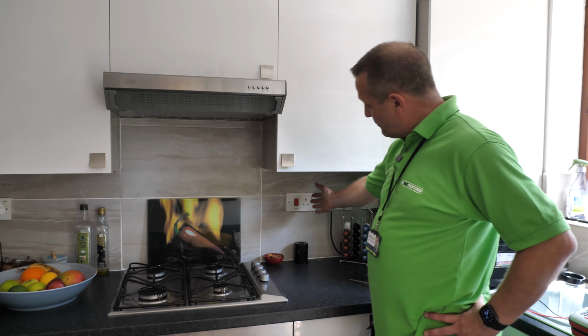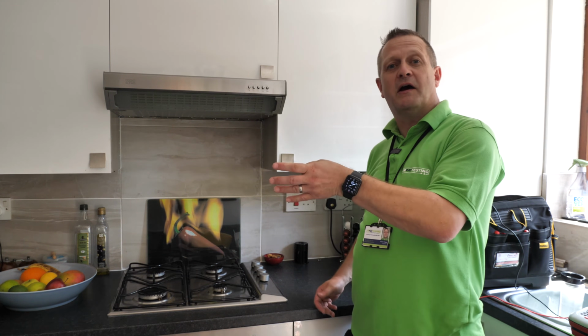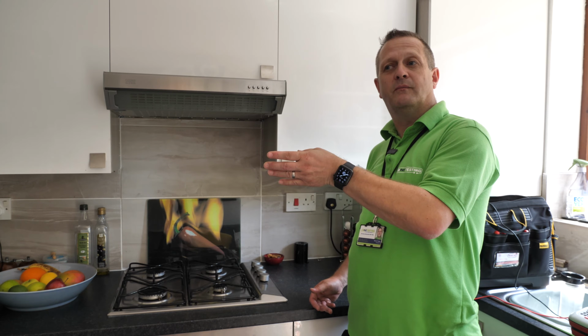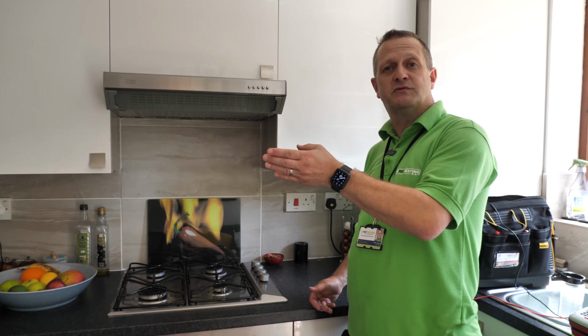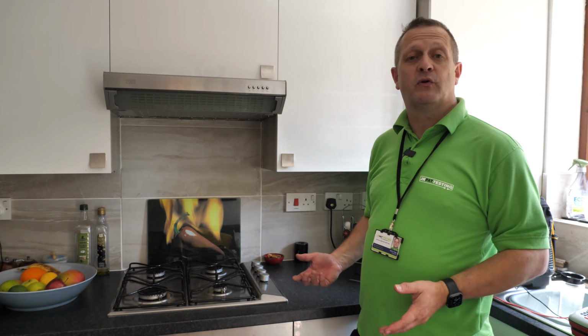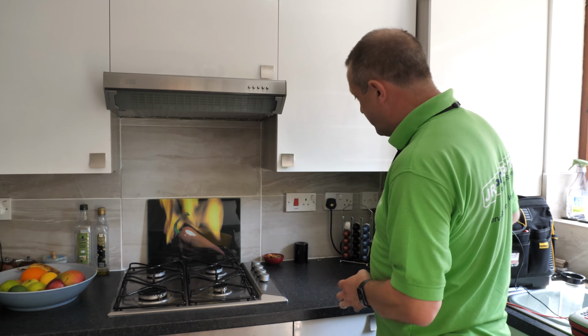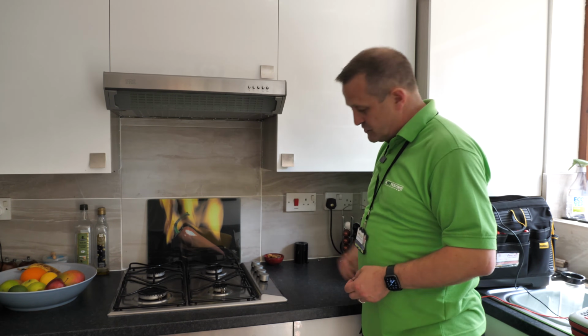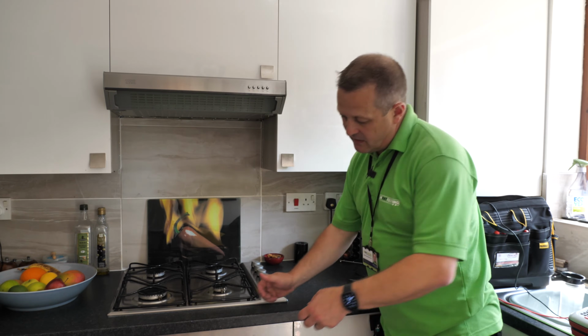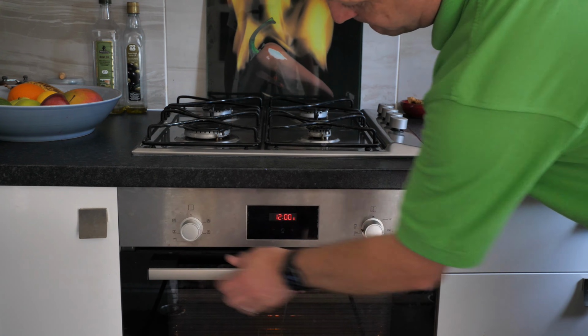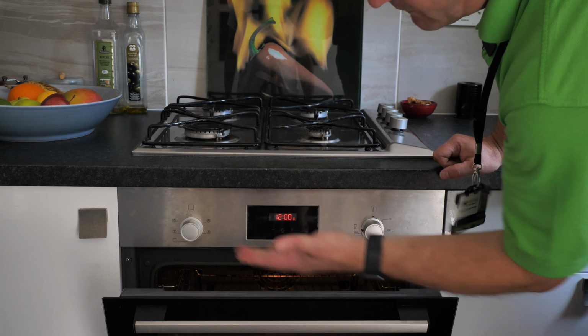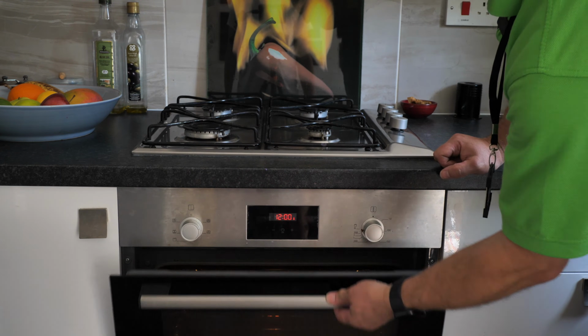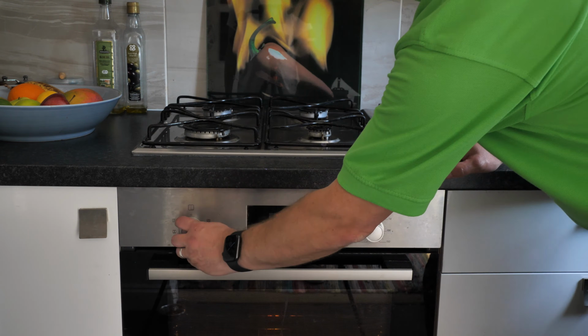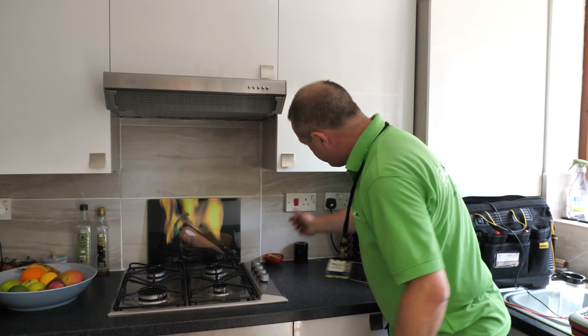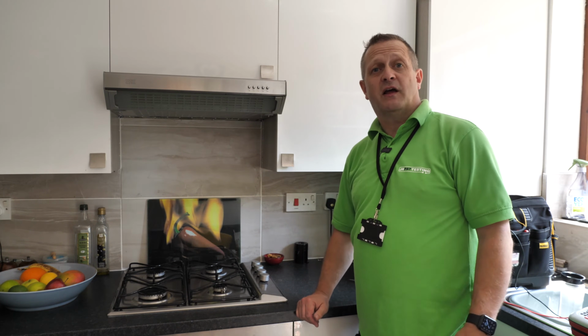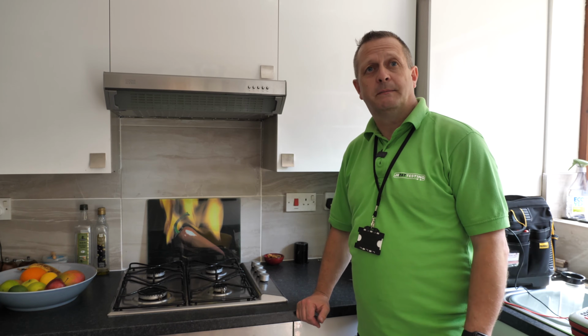Right, so now that we've put it all back together and at the consumer unit we've made all the switches live again, we need just to very quickly conduct a functionality check of the appliance. So switch the cooker on at the wall, and we can see that there's electricity coming through, and we're just going to make sure that the oven part is working, which it is, and so we can switch it back off again. And that is then the test for that class 1 fixed appliance complete.